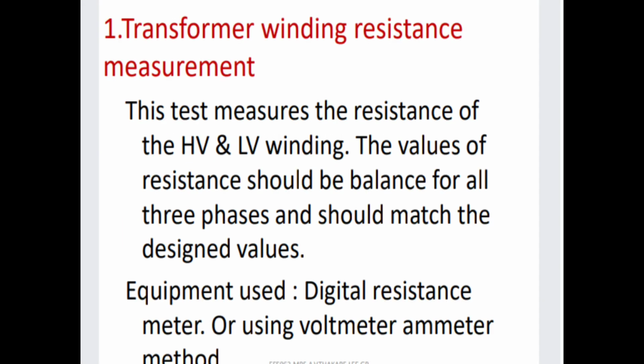Now transformer winding resistance measurement. First, this test measures the resistance of the HV and LV windings. This test is included in the type test and also the routine test. This test measures the resistance of HV and LV windings, meaning high voltage winding and low voltage winding. The values of resistance should be balanced for all three phases and should match the design value. Equipment used for this test: digital resistance meter or the voltmeter ammeter method.